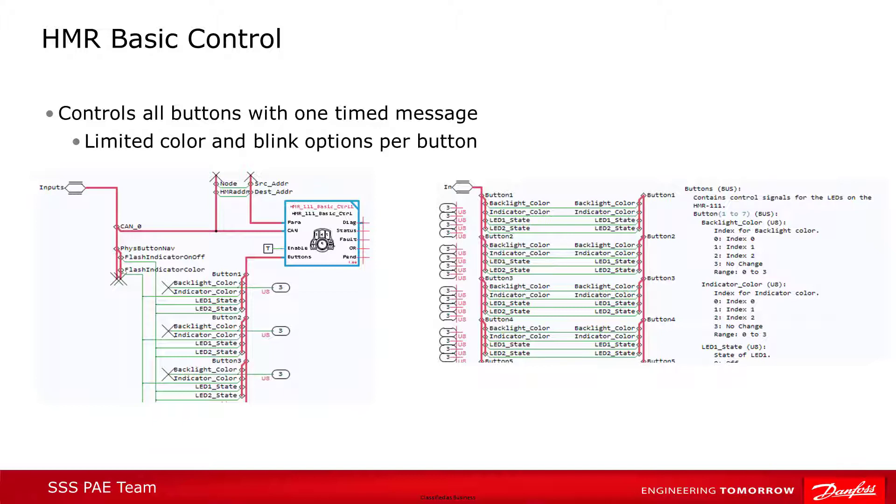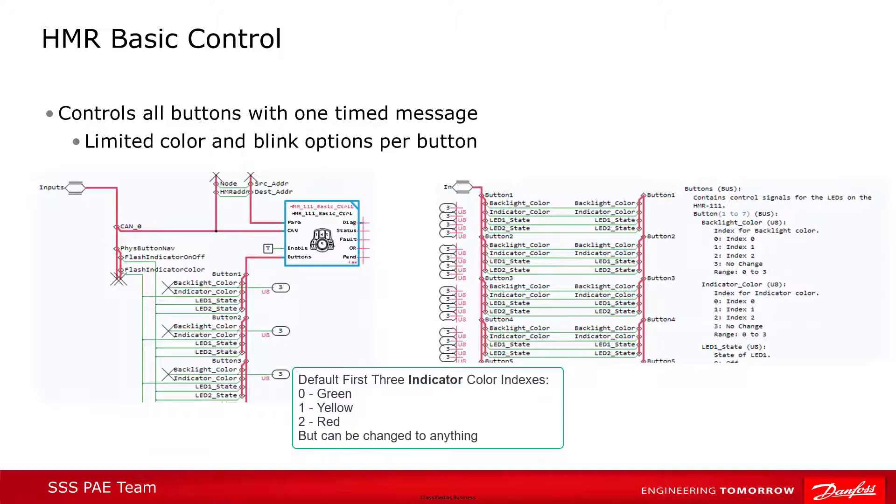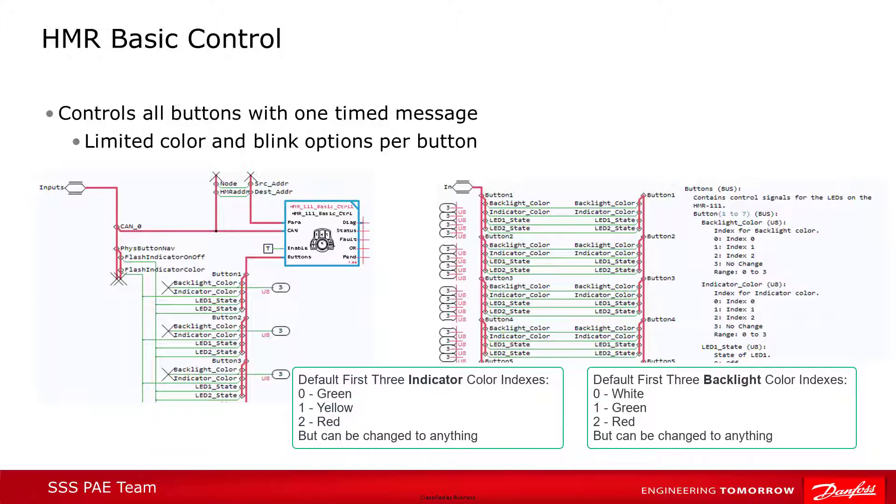The easiest way to do that is to use the basic control block. This block sends color and blink information for all the buttons in one message. Since it uses only one CAN message to send the information, there's a limited range of options that can be chosen. For colors, only the first three color indexes can be used for both the indicator lights and the backlight, in addition to the NO CHANGE command.